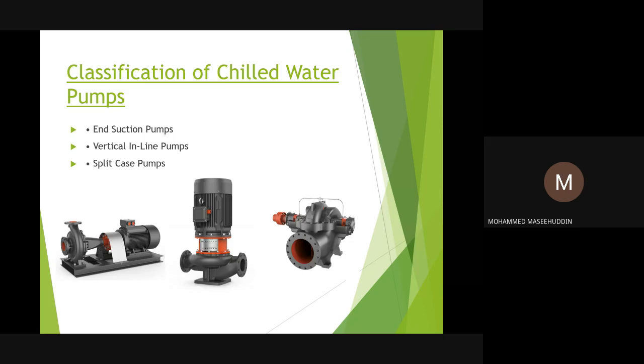So that's the reason why it's made for the primary circuit, and it has a pressure rating of up to 16 bar, which means if the system pressure in the building is, let's say, 6 to 7 bar or 8 bar, this pump can easily handle those kinds of pressures. So it is used mostly in the primary circuit of the building. And then you see the other pump, the second pump, which is vertical inline. Sorry, for the end suction pump, the suction is from the horizontal side. It has a horizontal suction and vertical discharge, top discharge.